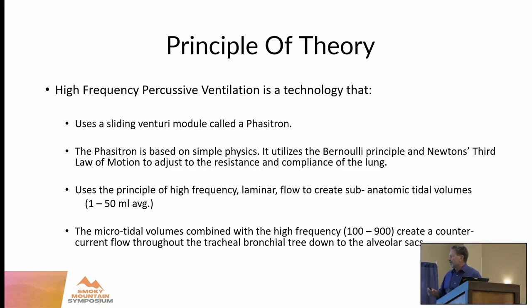It uses the principle of high-frequency laminar flow to create sub-anatomic tidal volumes, on average between half a milliliter up to 50 milliliters per pulse. This device is FDA approved for use from premature infants to the largest adult.